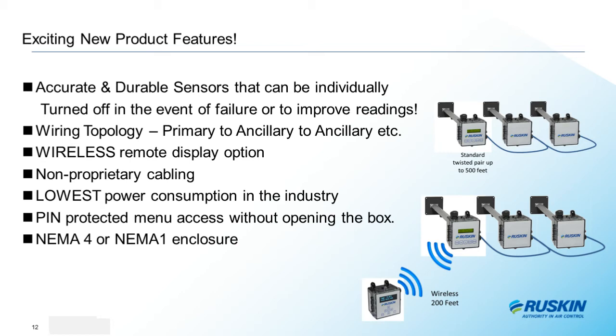Non-proprietary cabling, no more 50-foot coils of wire wrapped around the transmitter box. We've all seen that on the job site. Wire can be replaced or extended in the field without returning the probe for calibration and paying big bucks for wire you don't need. 2 probes with 8 sensors each consumes less than 8 VA. That's an incredibly low amount of power.